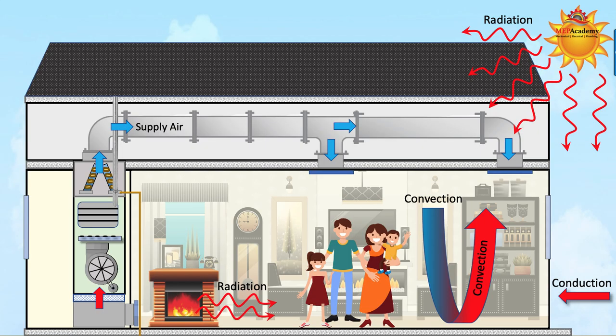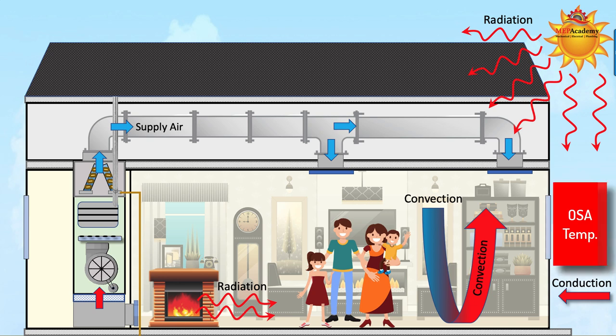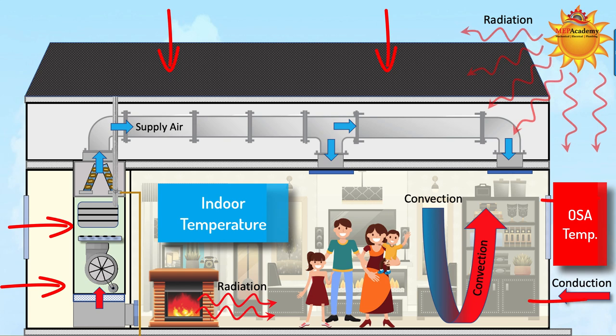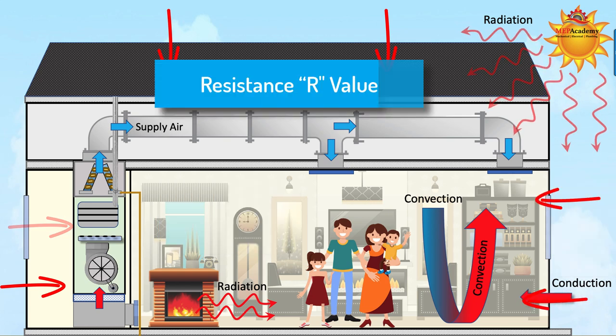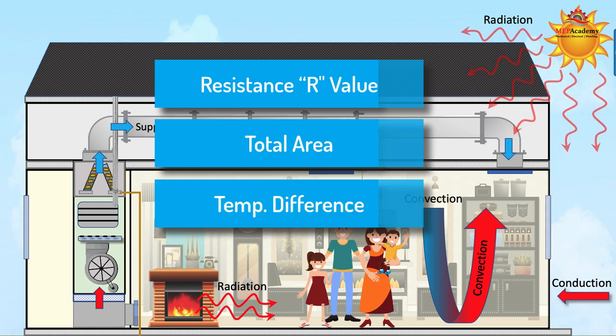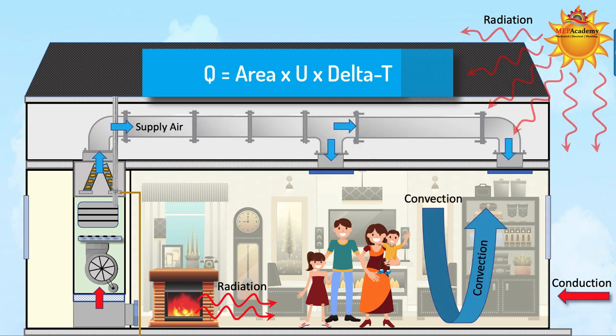Conduction occurs constantly in the home or office when the outdoor temperature surrounding the walls, windows, and roof is different than the indoor temperature. The heat will move through the construction materials at a rate defined by the resistance or R-value of the material, the total square feet, and the temperature difference between outdoors and indoors. Q equals A times U times delta T.